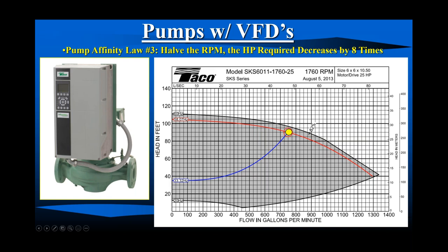So here's our pump curve, and we have a system curve, right? The more water we try to put through our system, the more resistance to that flow there is. So here's our design day. I don't know what it is, 750 roughly at 90. There's our design day system curve. Very rarely are we on design day, 2% of the time, let's say, in heating. So our two-way valves, or some of them, are going to close. What does that do to our system curve? Well, it pivots this system curve, this light blue line, around 0 GPM, 0 head, counterclockwise. So as two-way zone valves close, that curve pivots counterclockwise.